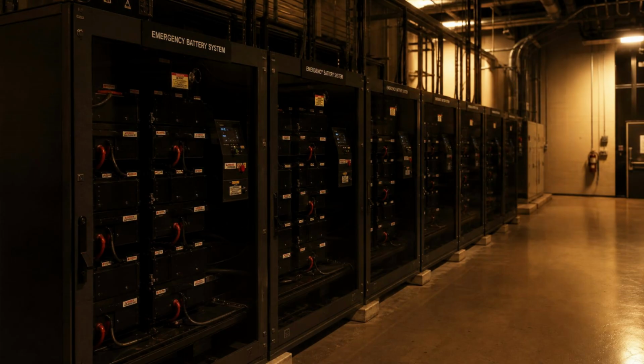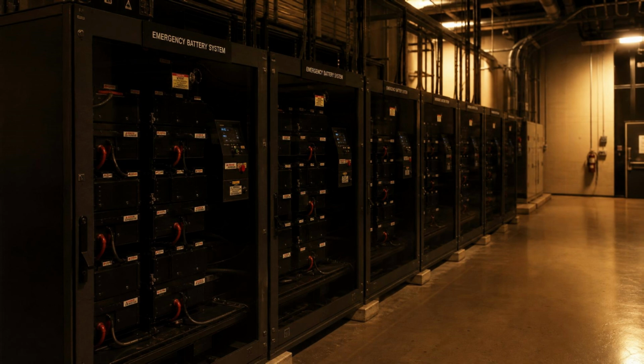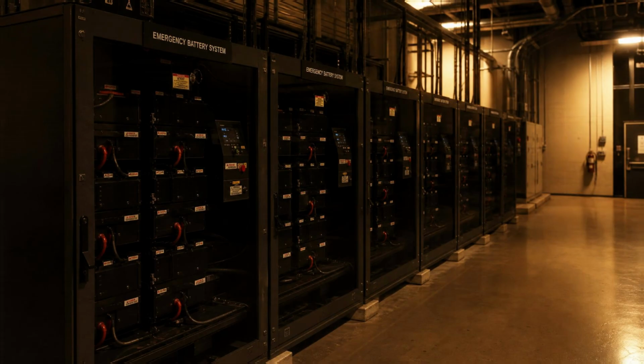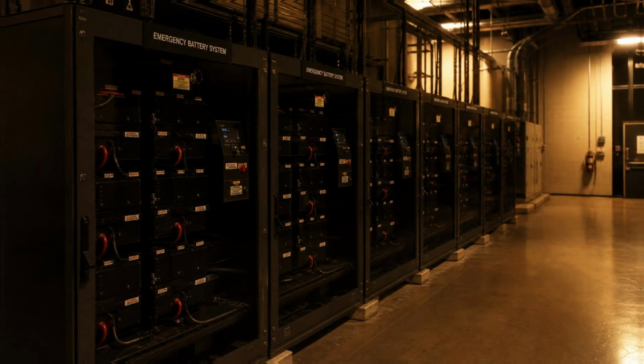In a building's emergency power infrastructure, batteries appear in many forms and in many places. We have already spent time with the large battery strings inside the UPS cabinet and with the smaller cells inside individual emergency lighting fixtures. But batteries appear elsewhere too, in roles that are equally quiet and equally essential. The generator's control system depends on a battery, typically a lead-acid unit, not unlike a heavy-duty automotive battery, to power the starter motor that turns the engine over during those first critical seconds of startup. Without that battery, the start signal from the transfer switch would arrive and find no energy to act on. The engine would not turn, the generator would not start. The entire carefully designed sequence that follows utility failure would stop at its first step.